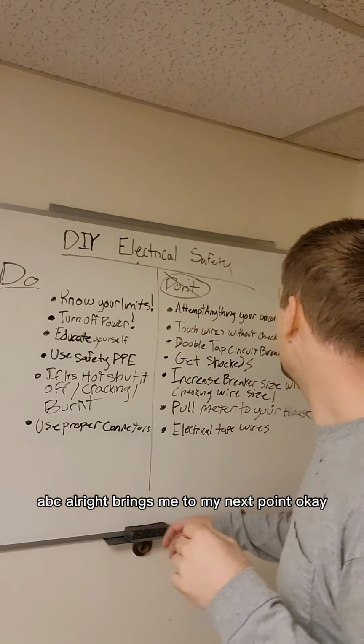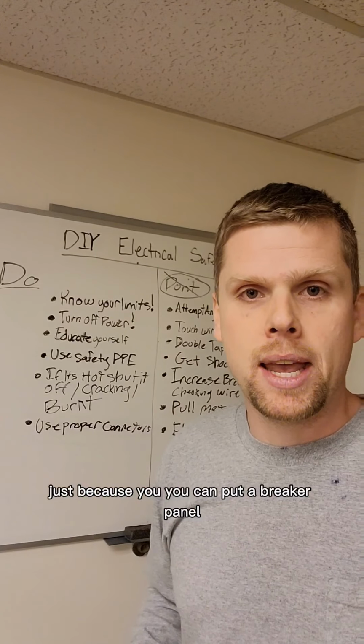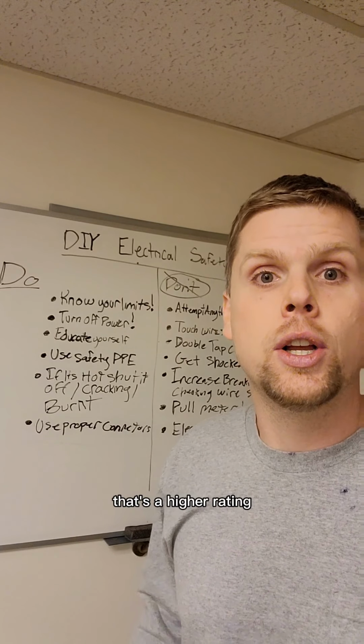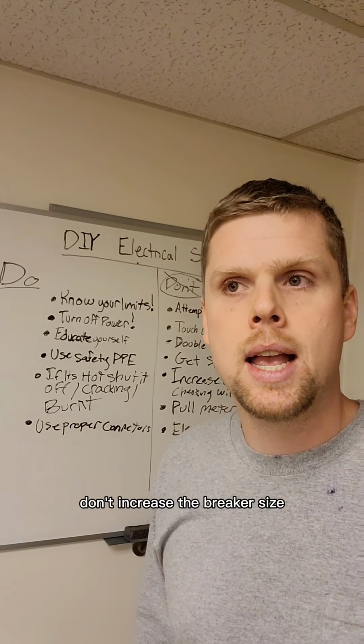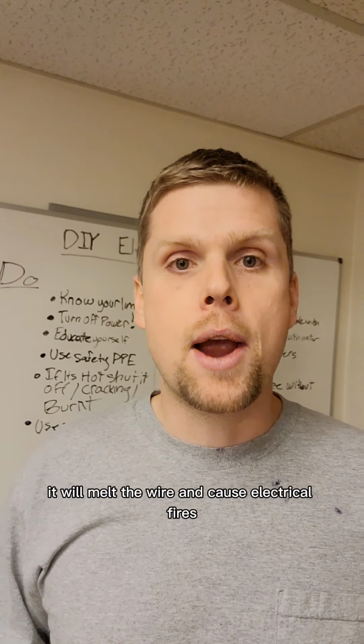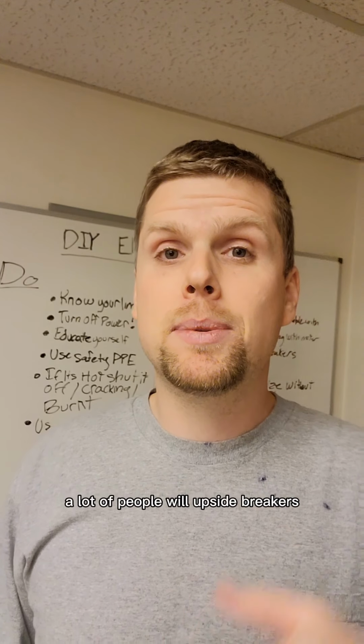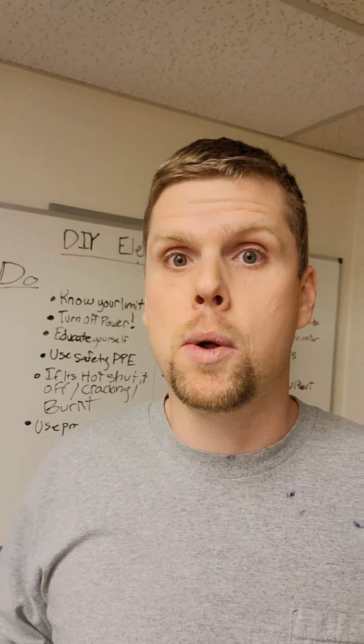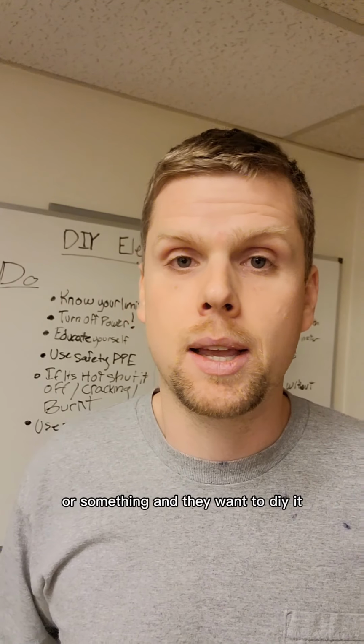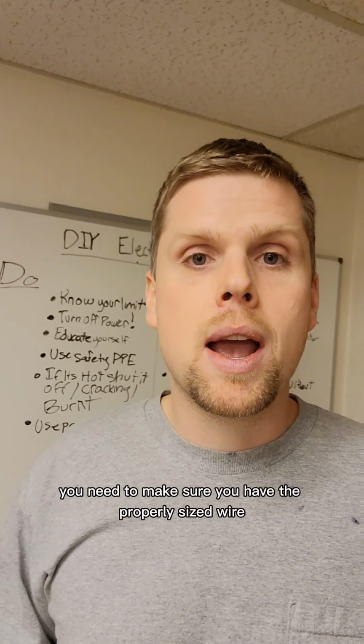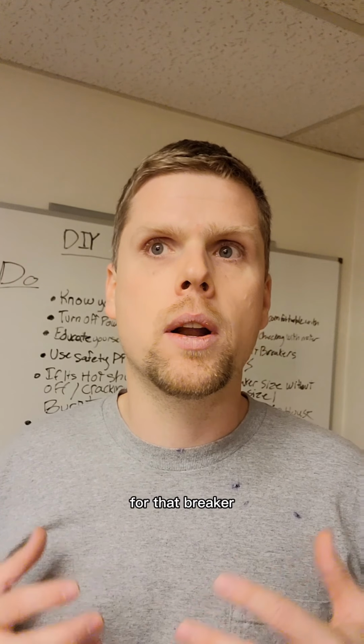Next point: just because you can put a breaker in a slot with a higher rating, don't increase the breaker size unless you're also increasing the wire size. Remember, circuit breakers are meant to protect the wire, not the fixture. If you draw too much current through a wire, it will melt and cause electrical fires. A lot of people upsize breakers because they want to put a big electric heater in their garage or something and want to DIY it. You need to make sure you have the properly sized wire for that breaker.